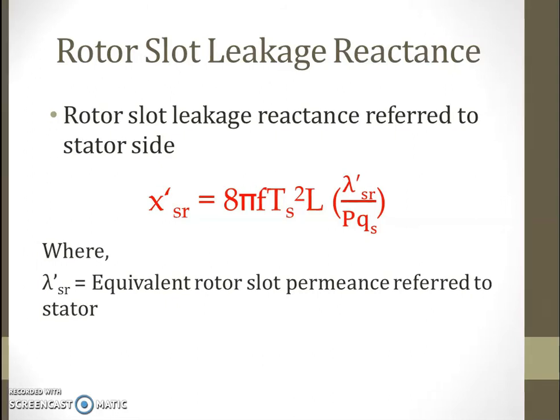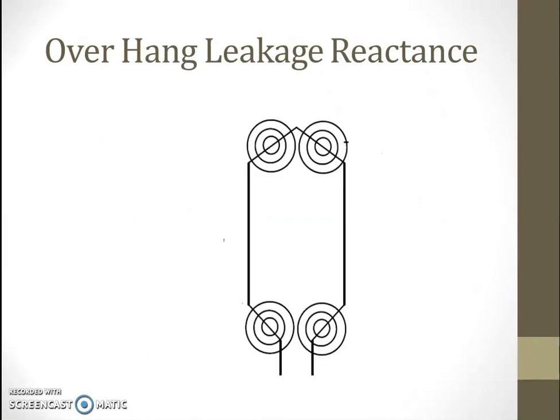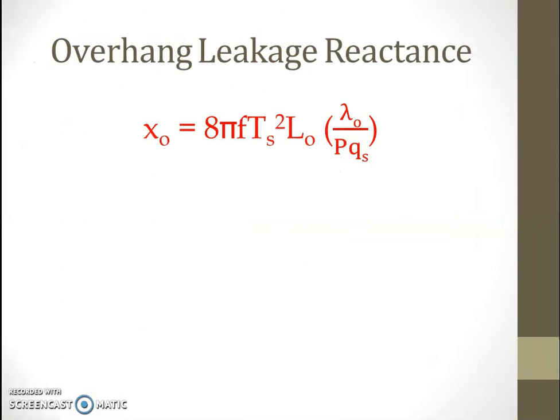Next is the overhang leakage reactance. In our figure, we have one coil with active length L, and some leakage flux known as overhang leakage flux. Overhang leakage reactance Xo is given by: 8·pi·f·Ts²·Lo·lambda_o / (p·qs), where Lo is the overhang length and lambda_o is the specific permeance of the overhang.